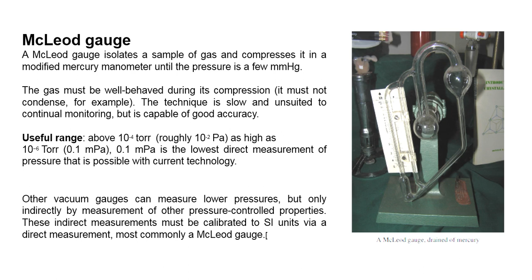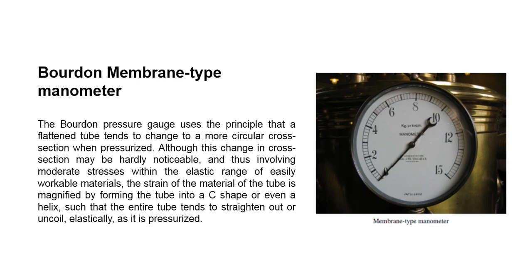Then we have another instrument, that is the Bourdon membrane type manometer. It uses the principle that a flattened tube tends to change to a more circular cross section when pressurized. Although this change in cross section may be hard to notice, it involves moderate stresses within the elastic range of easily workable materials. The strain on the material of the tube is magnified by forming the tube into a C shape or even helical. Hence, the entire tube tends to straighten up within the condition of elasticity as it is being pressurized. That's the working of the Bourdon membrane type manometer.